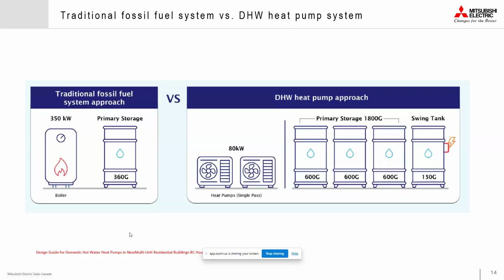That's one advantage also. If you can use the lower capacity or lowest capacity required for the hot water heat pump, especially in the existing building, you don't need to upgrade your electrical installation or any infrastructure. That will be a big cost, especially if you are looking for all electric heating.